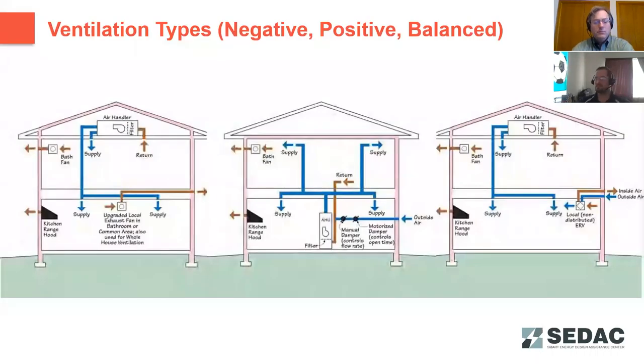So moving on to ventilation types for buildings, there are 3 different schools of thought on how to ventilate buildings. You've got negative pressure ventilation, where you've got an exhaust fan that runs, depressurizes the structure, and you draw in fresh air through leaks in the envelope and open windows and doors, essentially relying on leaks, gaps, and cracks to draw in that fresh air. The other option is positive ventilation, where you've got an outside air duct, usually tied into the return side of your air handler, so that that fresh outside air is brought in and conditioned and dehumidified or heated up as needed, and then distributed through the building. And then again, you're relying on leaks, gaps, and cracks in the envelope and some mechanical ventilation to relieve that pressure through the building. And then there's the balanced alternative where you've got an ERV or 2 fans, a supply and an exhaust that are bringing in outside air balanced with the amount of exhaust air going out of the building.